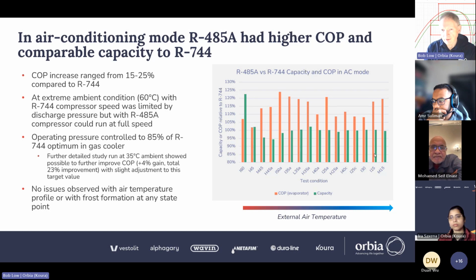So 60 C is a hot summer's day and you're stuck in a traffic jam. And 15 C is a more typical spring to autumn type temperature in most of Europe, where the cycle's running a lot more gently in terms of pressure. But you can see the orange bars here are the COP, and they're always better than 100%, and they go as much as 125%.